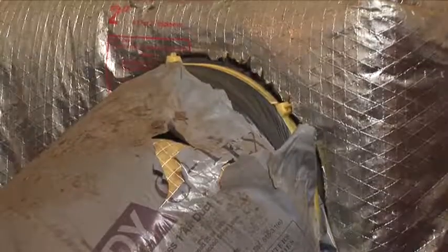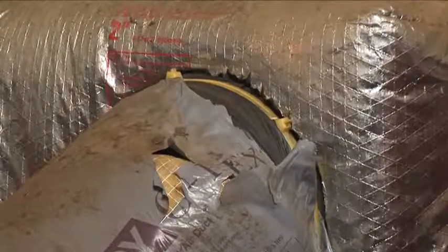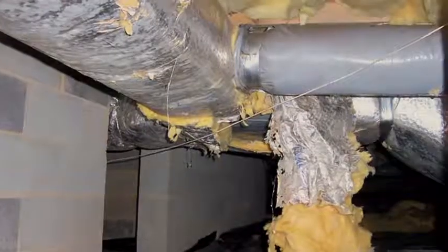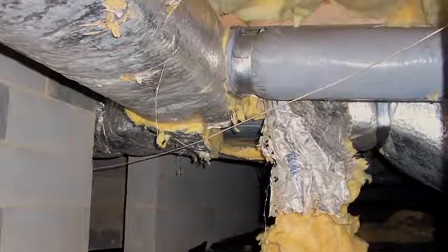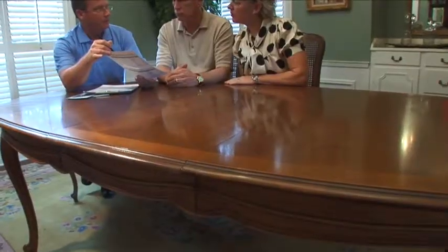And most of the duct systems are very, very inefficient. The average efficiency of a duct system in cooling is probably about 60%. So you're losing 40% of the cooling that you have. On this program, we'll explain why there can be so many problems with duct systems and their effects on your home's indoor environment and on your wallet. We'll also explain what you should look for when hiring a contractor to make improvements.